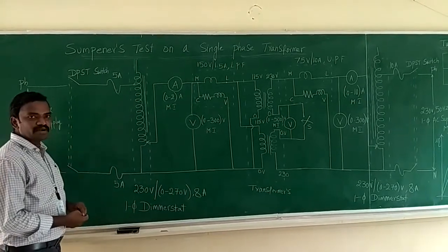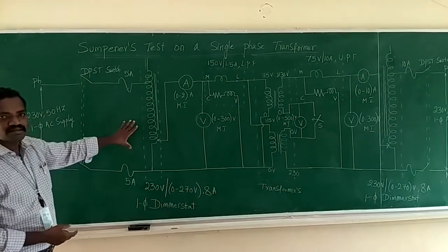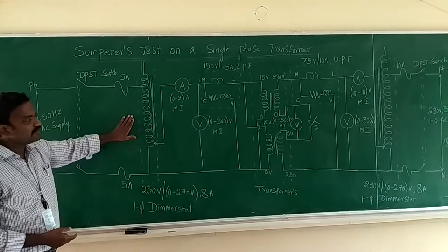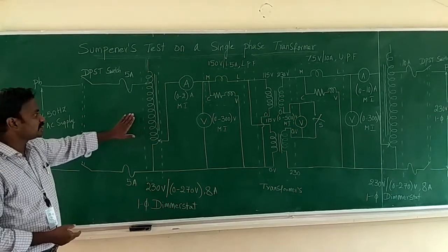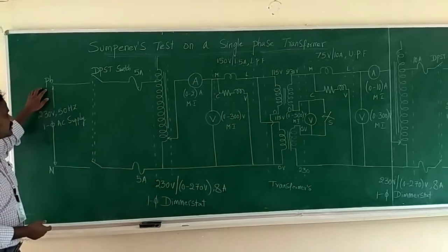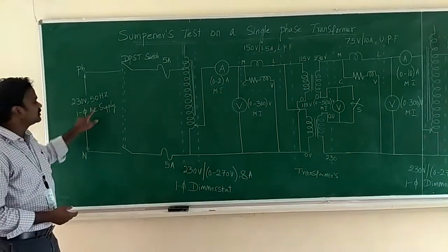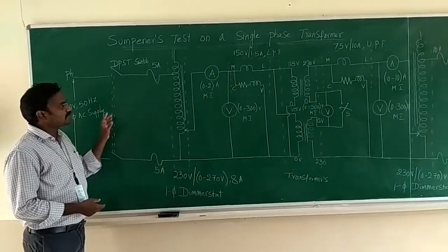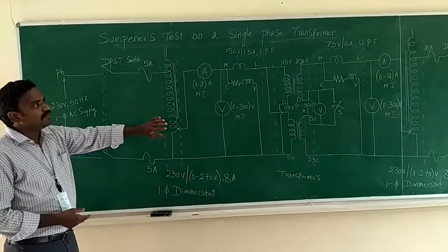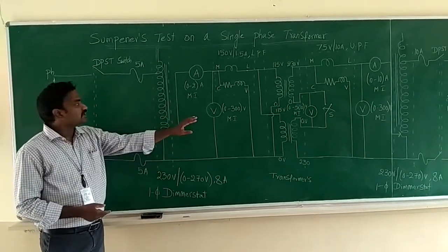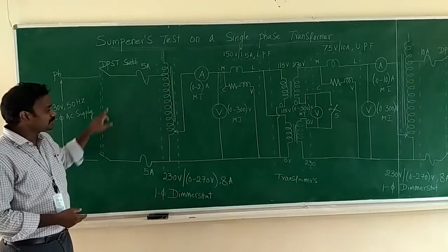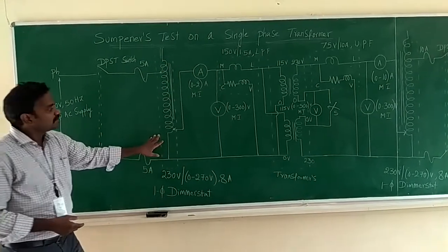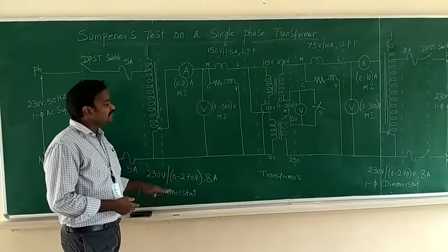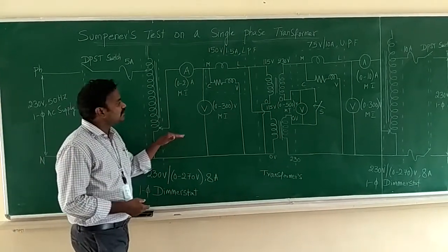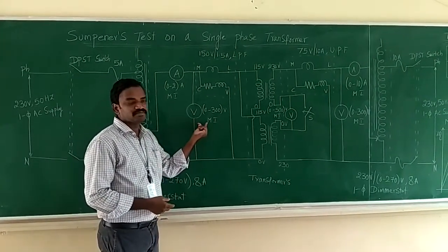So coming to the circuit diagram, this is the circuit diagram. It has to be connected in this manner, and here the supply is 230 volts, 50 Hz single phase AC supply. After connecting the circuit and making the connections tight, close the DPST switch at the primary side, and by slowly varying the single phase dimmerstat or variac, the rated voltage has to be applied here. The rated voltage is 115 volts.